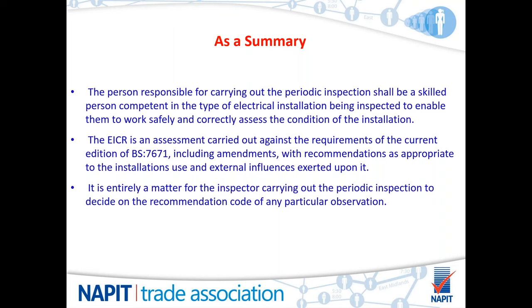And an EICR is an assessment carried out against the requirements of the current edition of BS 7671, including any amendments, with recommendations as appropriate to the installation's use and the external influences exerted upon it. So it is entirely a matter for the inspector who is carrying out a periodic inspection and test to decide on the recommendation code of any particular observation. As long as that person has substantial evidence to bring to the customer's attention and say, well, this is this, this is that, then the codes do play a part in that.